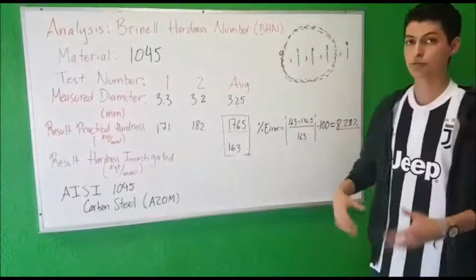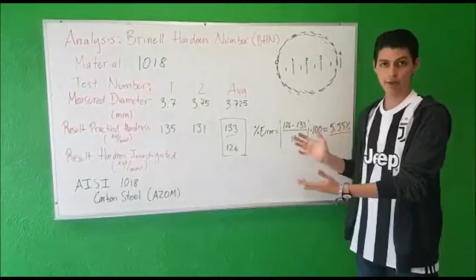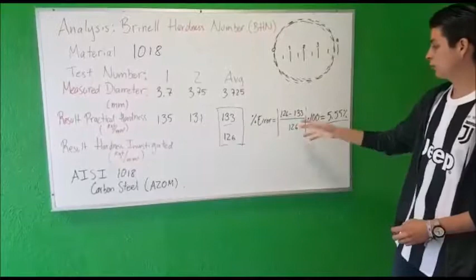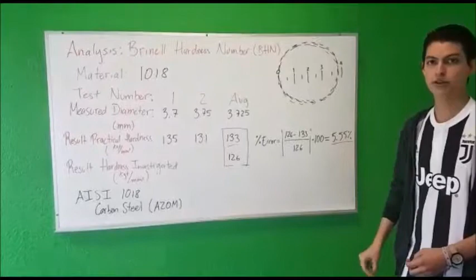The test we performed on the 1018 steel, which is in theory softer than the 1045, shows this in the diameter. It has a much bigger diameter than the last one, because the force causes a bigger indentation. The diameters we could make out were 3.7 and 3.75, which gave us this average. Then we searched each one in the tables and got an average of 133. And then we investigated the real result, which was 126 kilogram force over square millimeter, and we got a percentage of error of 5.55%.